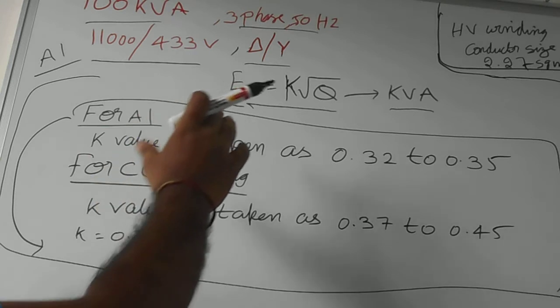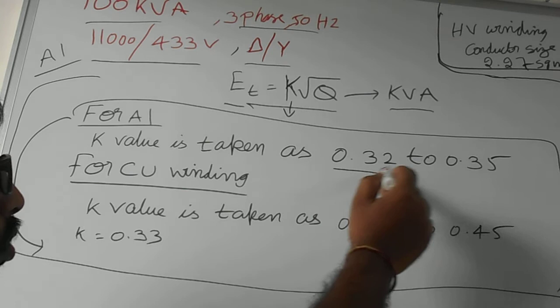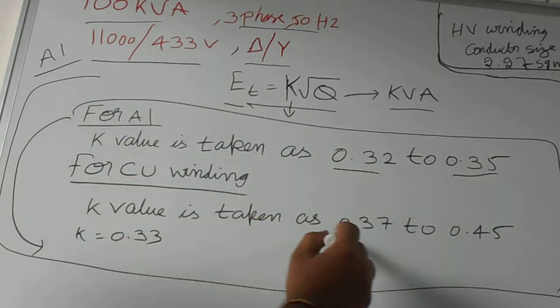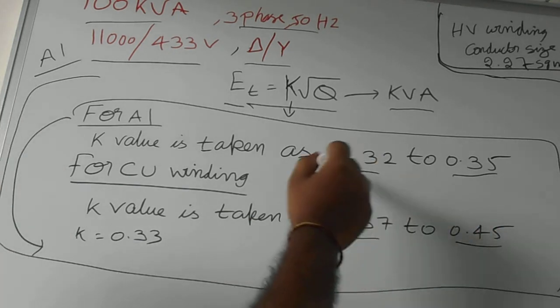For K, the value depends upon the nature of material, that is aluminum winding or copper winding. For aluminum winding the k value should be taken as 0.32 to 0.35 and for copper winding we have to take as 0.37 to 0.45. We can take any value between these numbers.